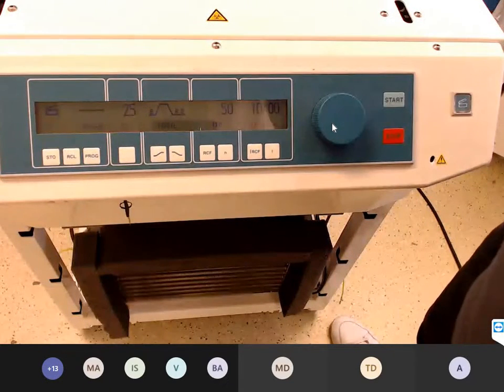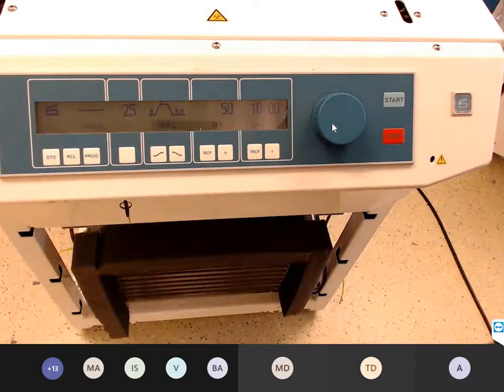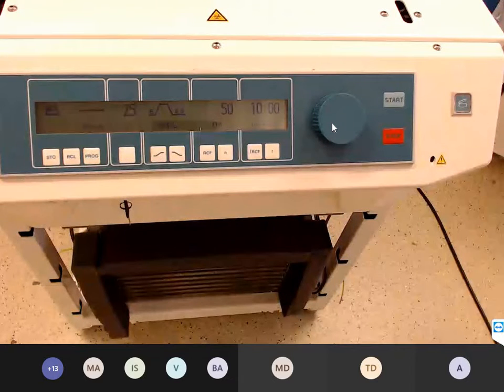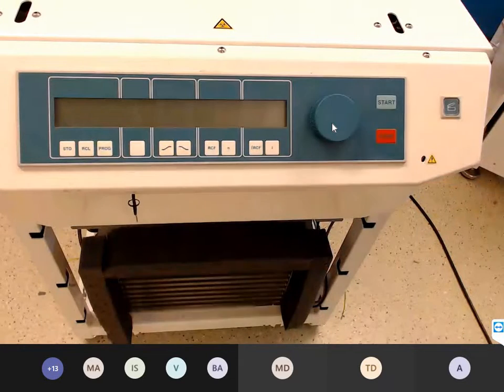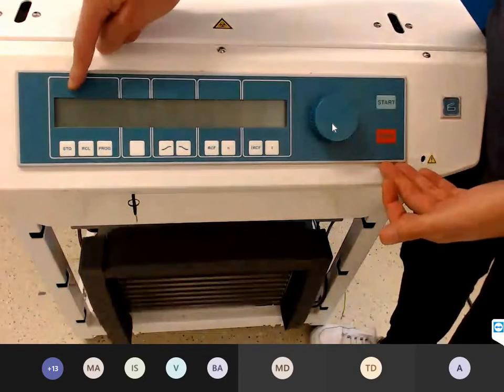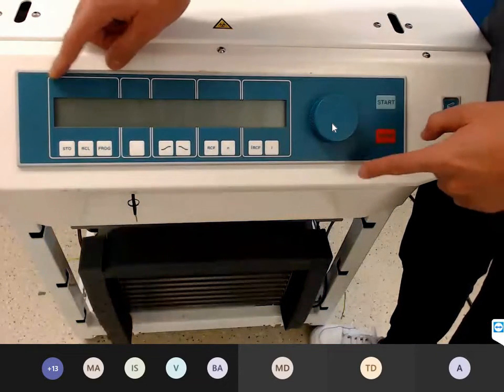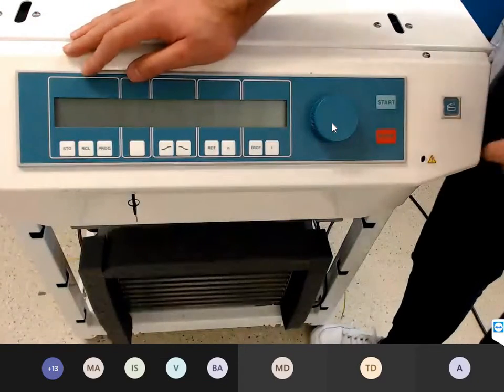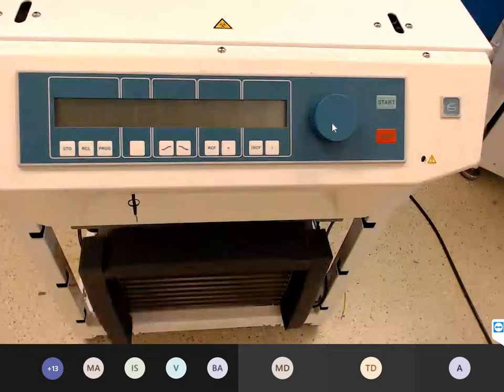Now I will show you the initialization and the offset settings. It's a little bit difficult, but it works. For this, switch off the device. If you replace, I repeat, if you replace a temperature sensor, you have to make an offset set. You have to adjust the offset settings. Or if you remove the control board also, you have to adjust the offset values.